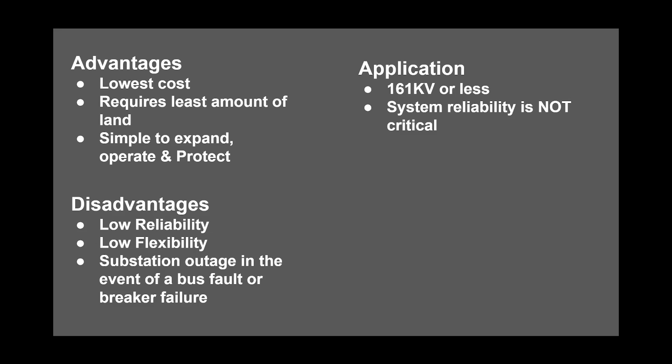And the application of the radial bus configuration is for substations at 161 kV or less, and for areas where system reliability is not critical.